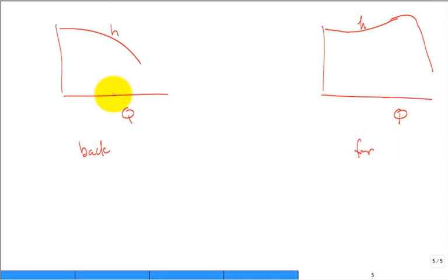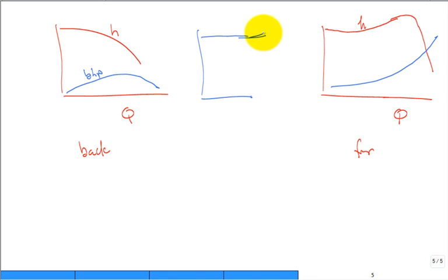All right, what about the power? The brake horsepower is going to go up and then back down. What about the brake horsepower here? And so we don't like that. It could be very high brake horsepower, and you could burn out your motor. What about the radial? Well, it's in between. So let's just put it in between so it's more flat, and then eventually a little bit of a hump, and then down. The brake horsepower is not as strongly going up, but more gradual growing up, flatter. But it still goes up. All right.